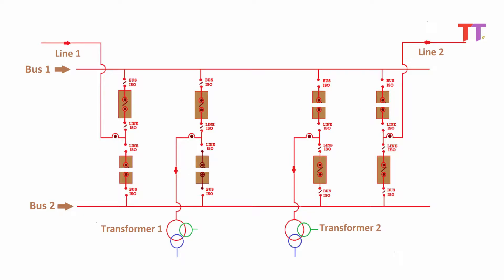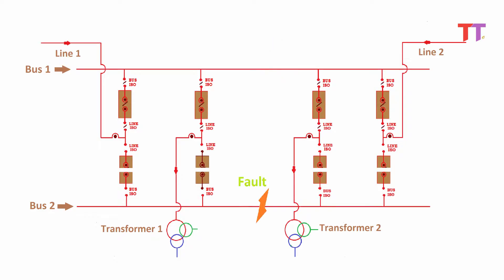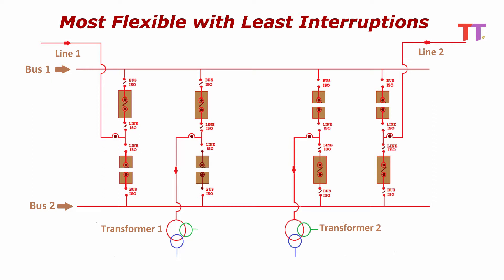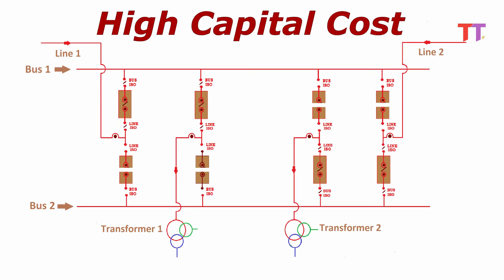To shift the load of transformer 1 from bus 1 to bus 2: first close bus 2 side isolators, close bus 2 side circuit breaker, then open bus 1 side circuit breaker and isolators. Hence the load of transformer 1 is shifted effortlessly. To shift the load back to bus 1, the exact reverse procedure is followed. In case of a fault on bus 1, the complete load can be shifted to bus 2, and in case of a fault on bus 2, the complete load can be shifted to bus 1, so there is minimum interruption in case of bus faults. Advantages: this system is the most flexible and causes the least interruption. Disadvantage: capital cost is very high as 2 breakers are required for each bay.